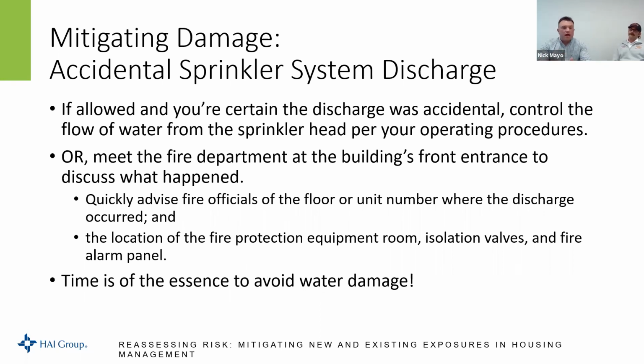So again, if allowed and you're certain that the discharge was accidental, that's a key point here. If you're 100% certain that the discharge is accidental, you can control the flow of water from a sprinkler head per your operating procedures. And again, those operating procedures would go through your fire marshal, fire prevention division, or your authority having jurisdiction. Or one of the best things that you can do is meet the fire department at the building's front entrance to discuss what happened.